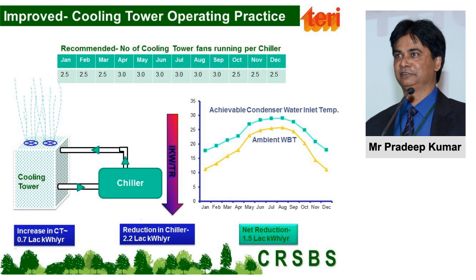But what will happen? If I'm operating more cooling towers, my consumption in cooling tower will increase. But on the other hand, my consumption in chiller will come down. And if the net result is saving, I think this is important and we should do it. We found that just by lowering the cooling water temperature, it is possible to save 1.5 lakhs of units every year.